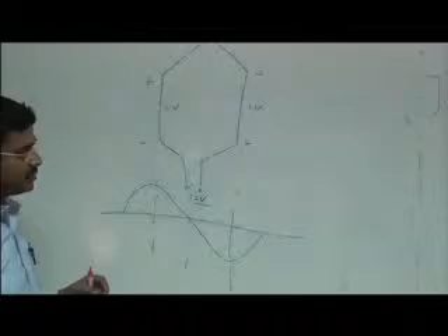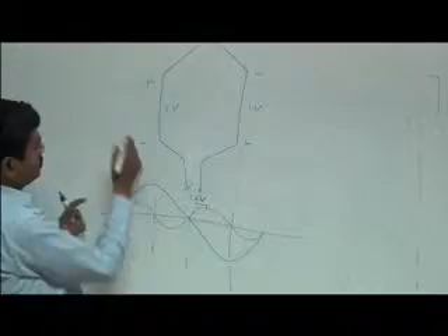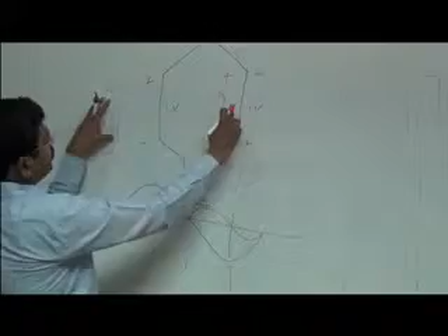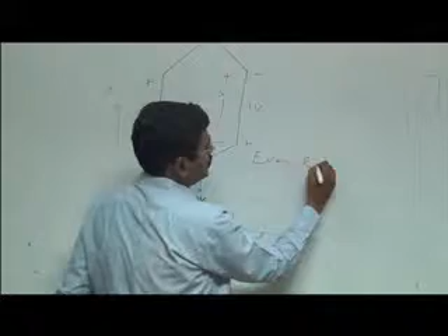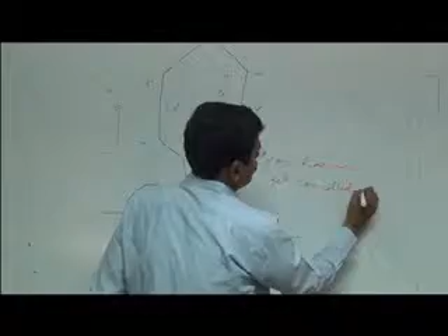Let's see what happens for the second harmonic. We have to draw 2 complete cycles in one fundamental, and here we see that when this is positive, then 180 degrees after, the other conductor of the coil will also be getting positive voltage. So if this is plus minus, this will be plus minus, and the 2 voltages will oppose each other, and therefore even harmonics get cancelled. It means there won't be any even harmonics in our system. Now we are left with only odd harmonics.